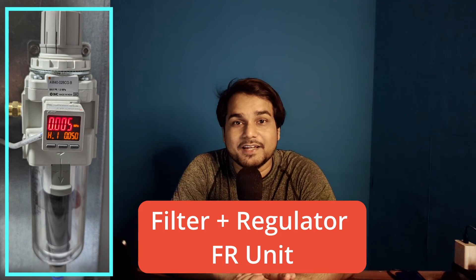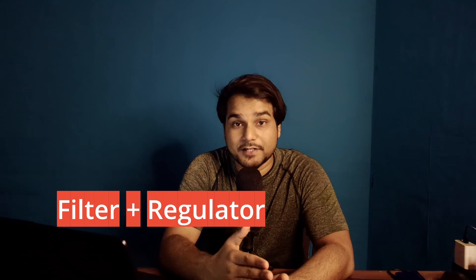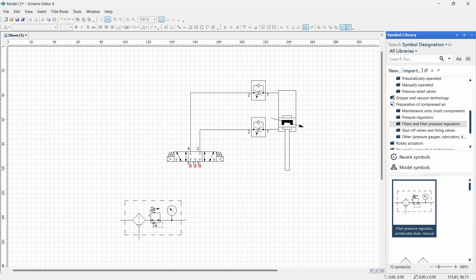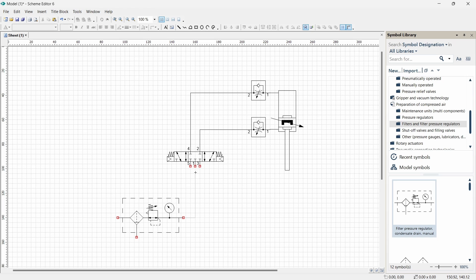To supply constant compressed air to the circuit we use a pressure regulator, and we can add a filter module to create an FR unit. We can also add a lubricator to mix lubrication mist into the compressed air to lubricate actuator moving parts, increasing cylinder life — creating an FRL unit. However, some manufacturers recommend not using an external lubricator because their cylinders come pre-lubricated; adding external lubrication can damage the pre-lubrication and then require lifelong external lubrication. Always check before using external lubrication. Now I am dropping the FR unit and connecting its output to the solenoid valve input.